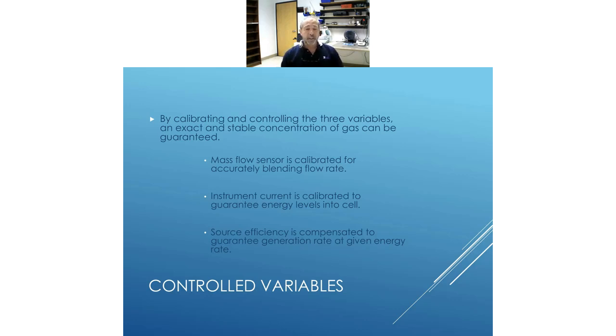Also, the current that is passed through these electrochemical cells has to be controlled as well. That gives us the amount of the gas in question, chlorine or chlorine dioxide in this case, to be blended with the accurate amount of air. And then the efficiency of the source also has to be compensated for or characterized so that we know exactly how much is coming out. They're not all 100% efficient.